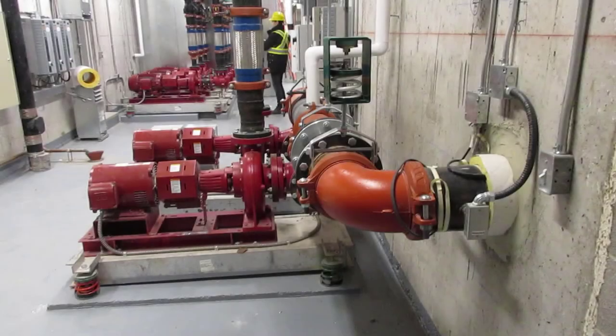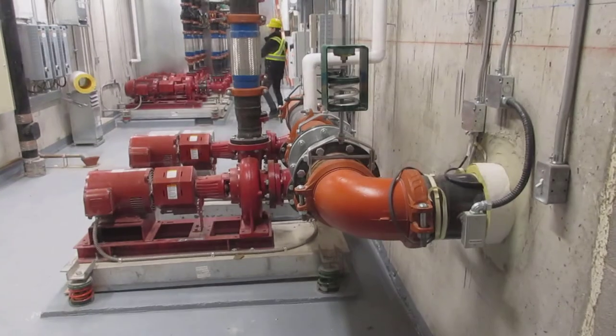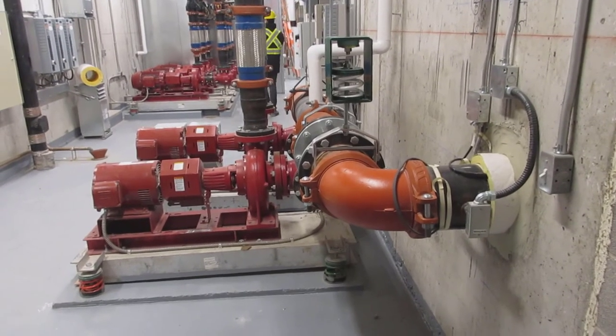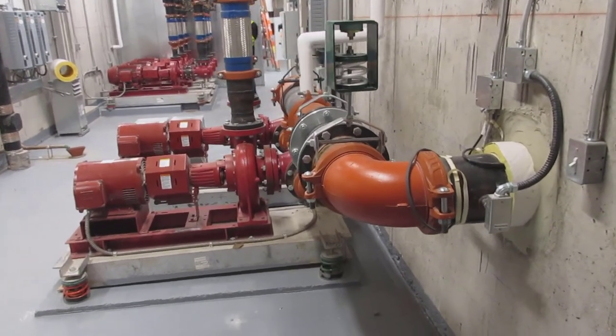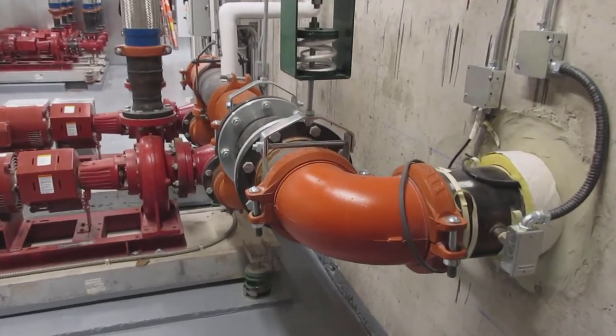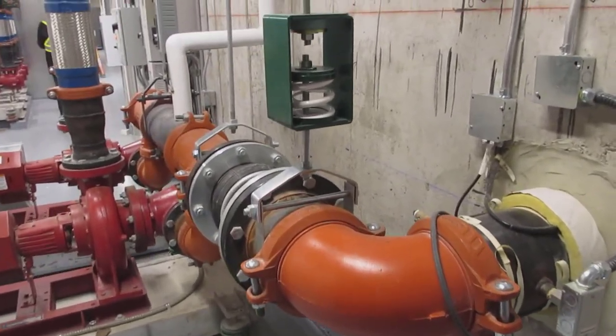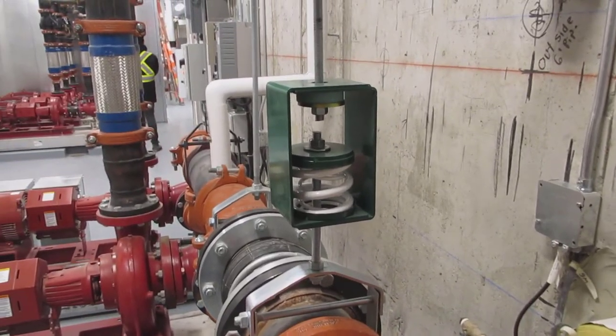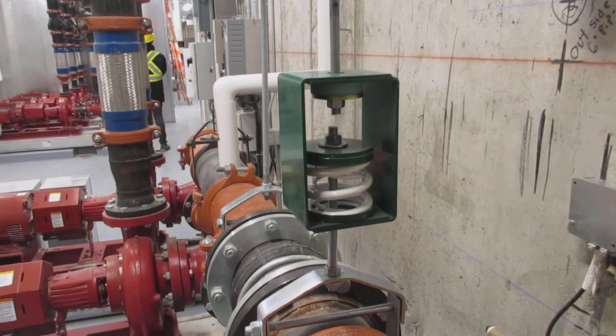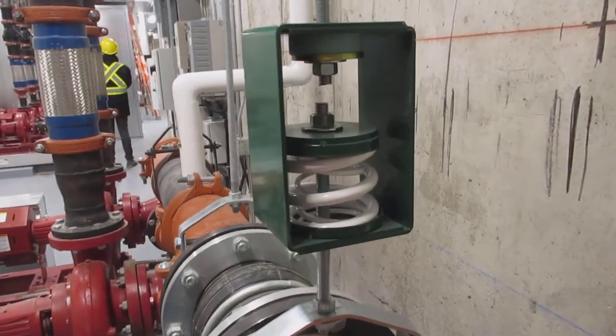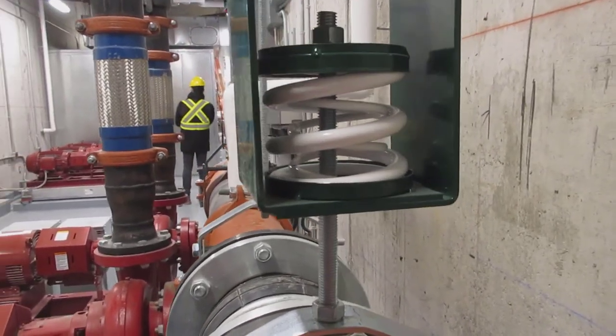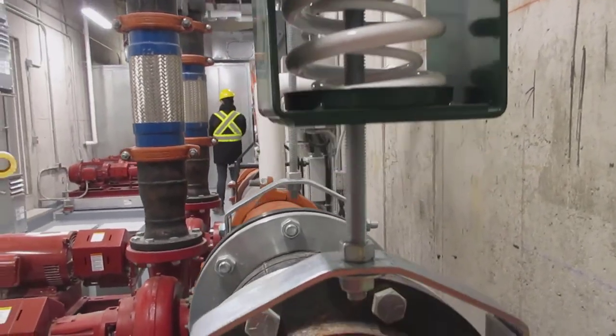So we'll take a look at some spring hangers installed on condenser water pipes. We've seen these before in some other videos we've done on other isolation products shown here, but now we're going to talk about them. The first isolator is an SH-R-1S1100. There is a white spring inside a white outer spring and there is a green rubber element at the top.